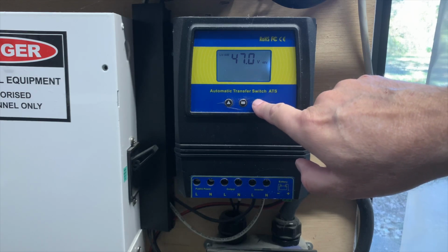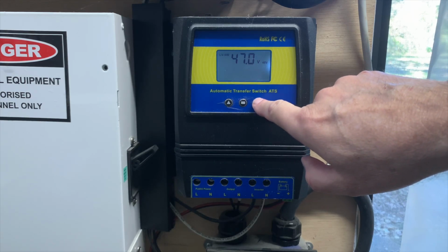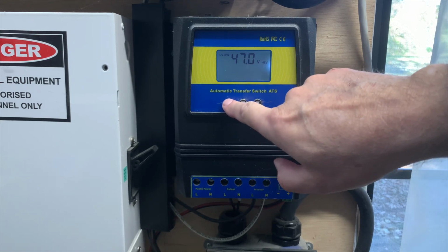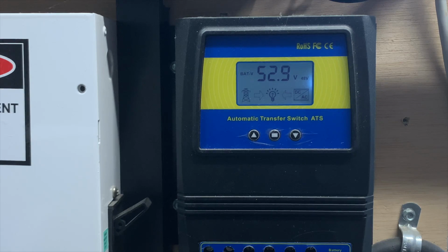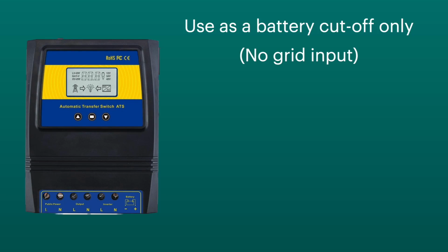So if your battery level goes below what you set before as your low voltage switch voltage level, then this switches from inverter to the grid, but there's nothing connected to the grid. So you've disconnected your inverter from your load, which keeps your battery from getting drained down too far. And a good use of this would be lead acid batteries that don't have a BMS, but you still want to keep those batteries from getting down below. And in case of a lead acid, you don't want it to go below 50%. You're automating the protection of the battery, so you don't have to keep your eye on it all the time.